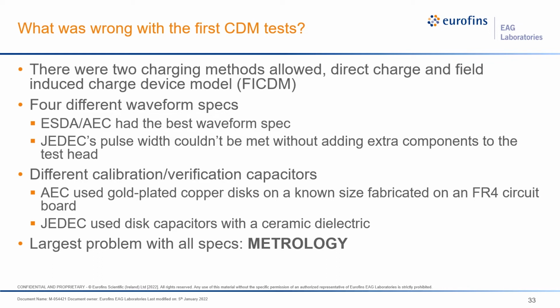For calibration verification capacitors, the AEC and ESDA used an FR4 PC board with a simple pattern on it - a gold-plated round copper pad of a known size. This created the capacitor for the calibration/verification. It was inexpensive and easy to make. But because FR4 changes characteristics when it absorbs moisture, and because it warps easily, this wasn't a good solution. JEDEC used more expensive disc capacitors with a ceramic dielectric, which are much flatter and much more stable.